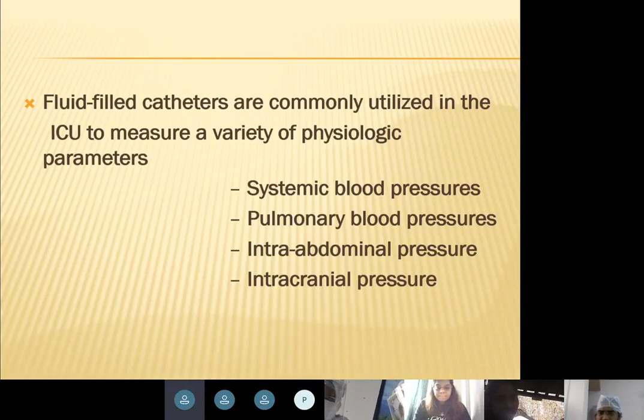Any system in our body, in this fluid filled transducer system, will have these parts. You'll have a catheter, connecting tubing, stopcocks, pressure transducers, a continuous flush device, and an amplifier, oscilloscope, processor, and recorder. These last four things, amplifier, oscilloscope, processor, and recorder, are the electrical system, which is there in the monitor, whereas the first ones, intravascular catheter, connecting tubing, stopcocks, pressure transducer, and continuous flush device, lie outside.